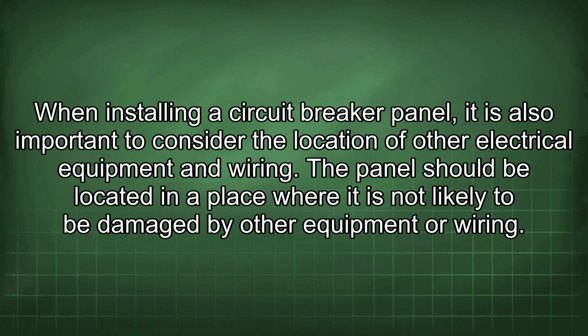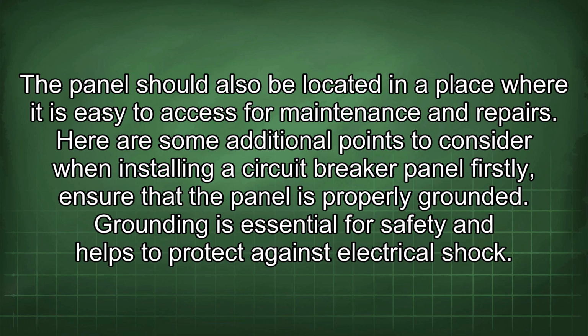When installing a circuit breaker panel, it is also important to consider the location of other electrical equipment and wiring. The panel should be located in a place where it is not likely to be damaged by other equipment or wiring. The panel should also be located in a place where it is easy to access for maintenance and repairs. Here are some additional points to consider when installing a circuit breaker panel.